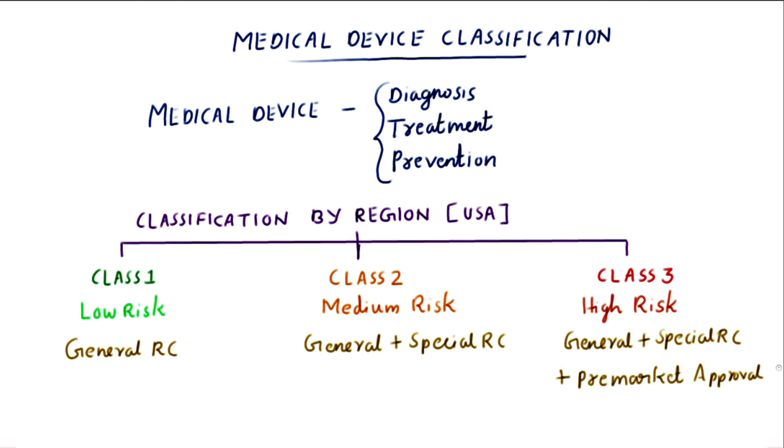Pre-market approval is the FDA process of scientific and regulatory review to evaluate the safety and effectiveness of Class 3 medical devices.